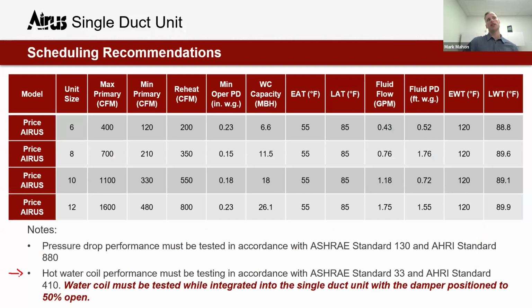And this would be something I would love feedback on from the group. If you have thoughts on a different approach, shoot Tom an email, shoot me an email. But what I would suggest is specifying and scheduling that the water coil must be tested while integrated into a single duct unit with a damper position to 50% open. That just means you're going to get straight goods from everybody. I think it's simple. I think manufacturers will have to conform to that if it's specified.